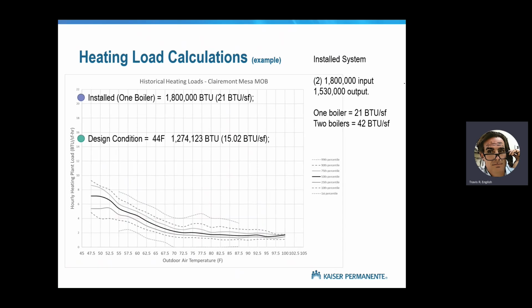Okay, so here's the loads. We had a few hours in the year where we got to 9 BTU per square foot, but the real number that you should be looking at is that average load. So when we're in the 40s, that number is about 7 BTU per square foot. So the ASHRAE load calculation is over by a factor of 2. And then more importantly, this boiler is installed at 21 BTU per square foot, and we're spending a whole lot of time in the system down at 2 BTU per square foot.